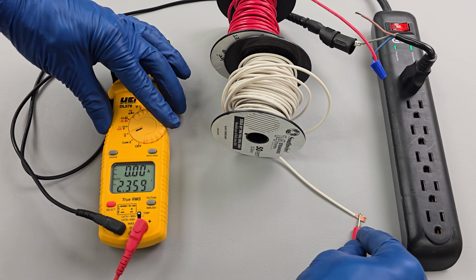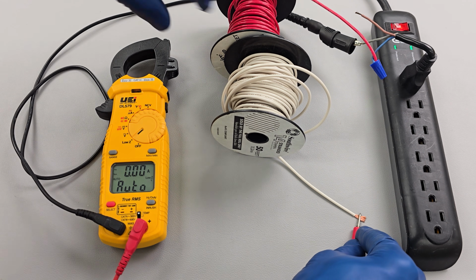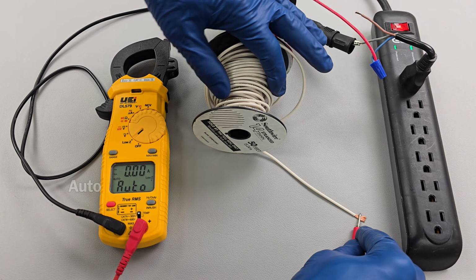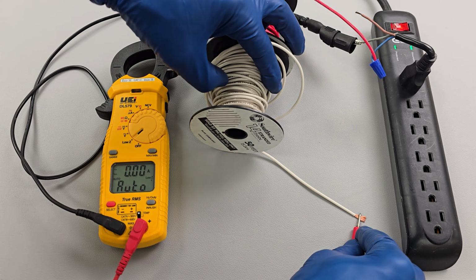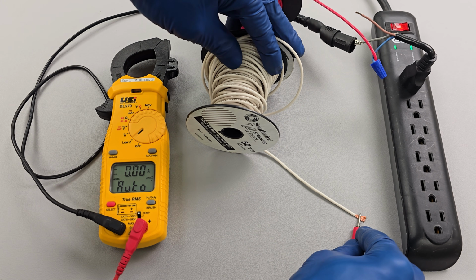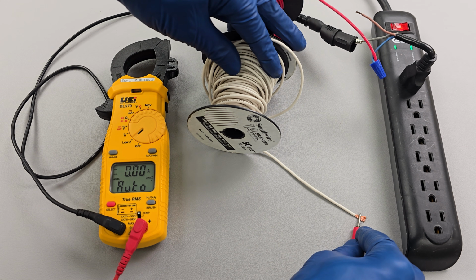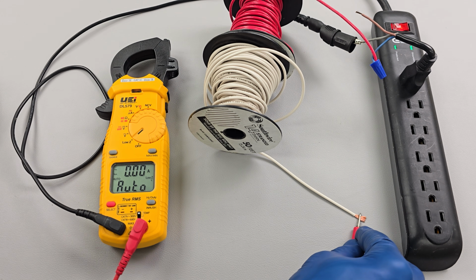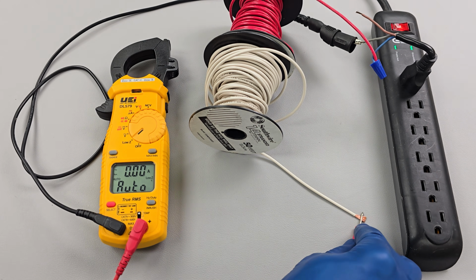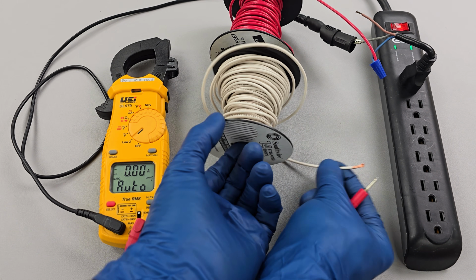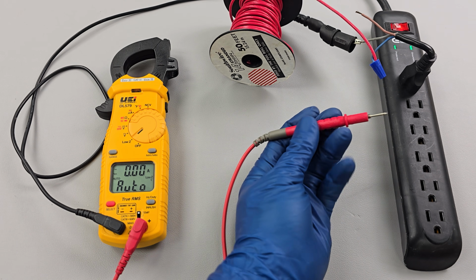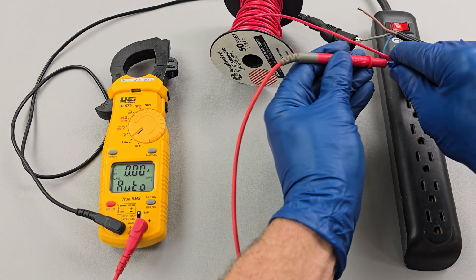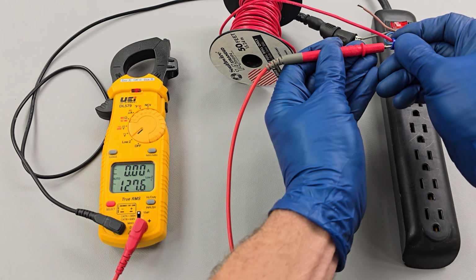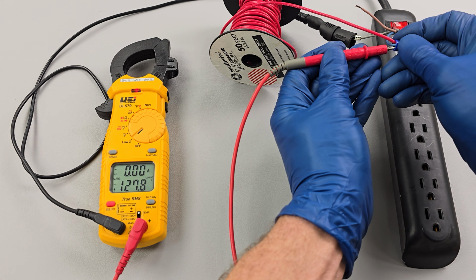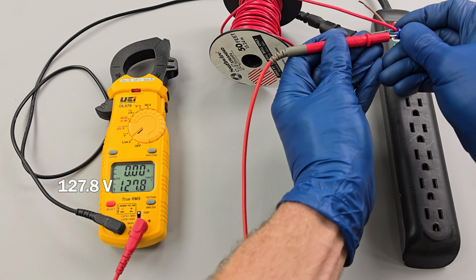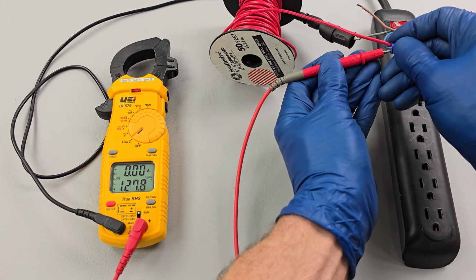Now, if we were going to turn this over to low Z, you now see it's just going to say auto, and it's not going to register any voltage whatsoever. So there's no voltage when the low Z function is used. And so you know that this is not a current carrying wire right here. So if we were going to measure right in here, you can see we're now measuring 127.8 volts, which is the true voltage.